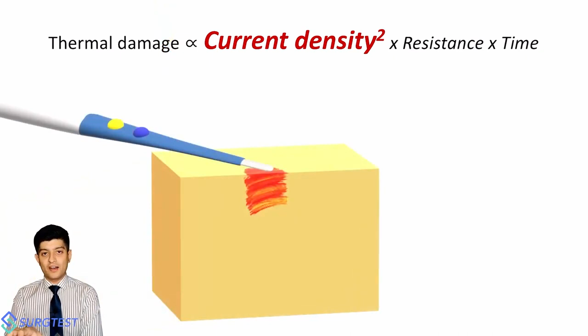Once again, if you're holding the active electrode with a very small amount of contact, or rather I would say near contact, there is something very interesting that ends up happening. If you apply a cutting current, again a low voltage continuous current, there is arcing of the current across air. So it's near contact, it's not actual contact. As a result of the arcing of current, there is a sudden delivery of energy to the tissues that usually reaches just over 100 degrees Celsius, which produces vaporization of the cells. This vaporization not only produces steam, but also releases a large amount of ions within the gas around the operative area. This plasma cloud of vaporized ions conducts electricity in turn, and that ends up causing a very high current density at the tissue site.